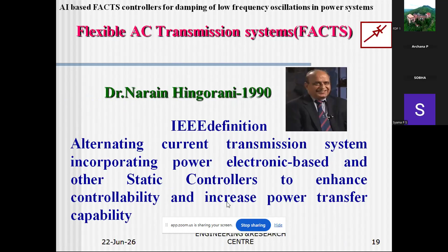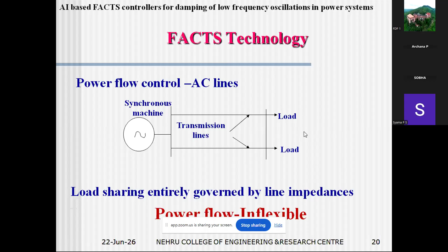So this is the definition. What exactly is it doing? Suppose you are taking a conventional system. You have a synchronous machine, a load, and two transmission lines connecting to the load. The natural sequence in which power flows from the machine to the load depends on the impedance offered by the line. Similarly, for the load, it is controlled by the impedance of that line. So load sharing is entirely governed by line impedance. You cannot have more power flow because the line impedance is rigid. You cannot add length to the line or cut off a particular line. It is all rigid, so the power flow in a conventional power system is inflexible.